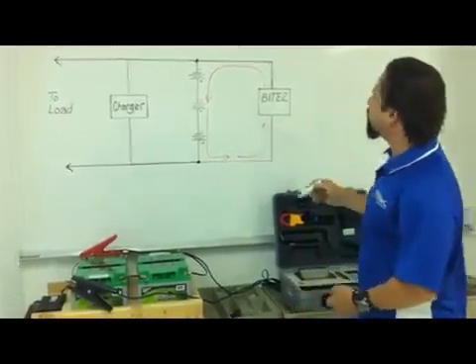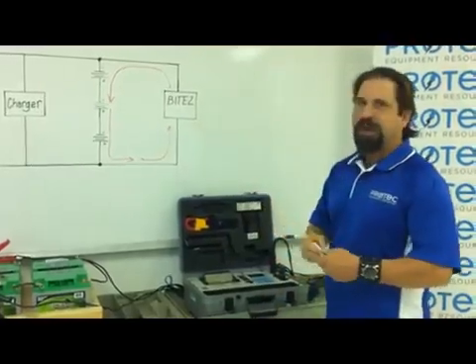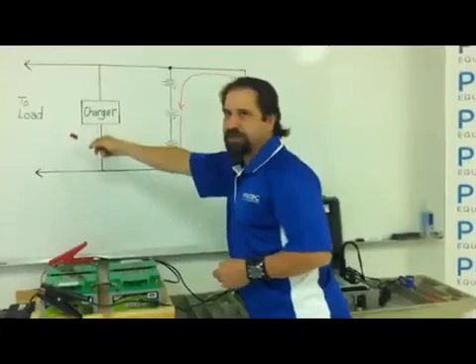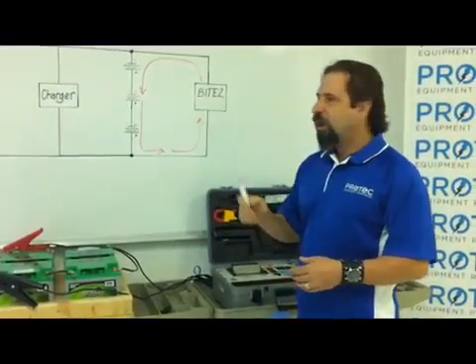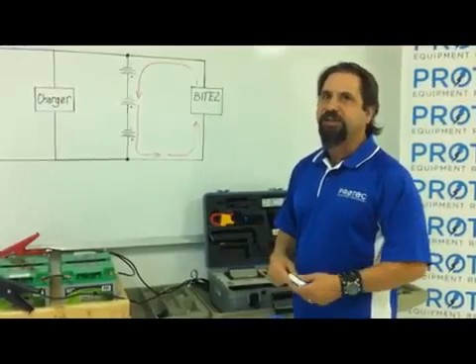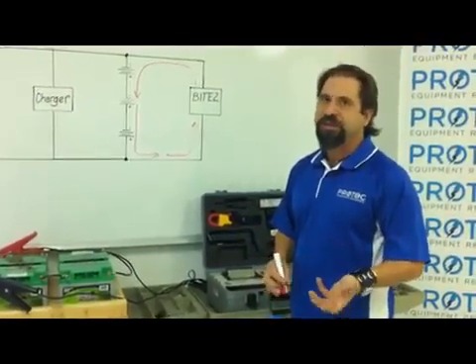All current should flow through the battery string back to the BITEZ, with no carryover into the load circuit. That means the battery bank can be tested while connected to the charger and to the load, and never have to be taken offline — which is one of the attractive features of doing the impedance test.